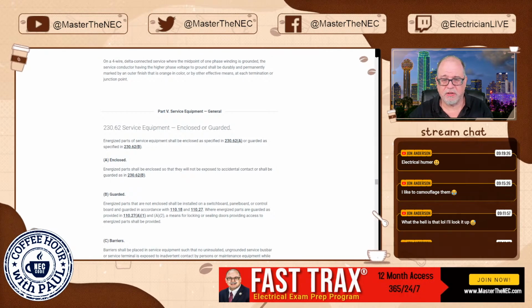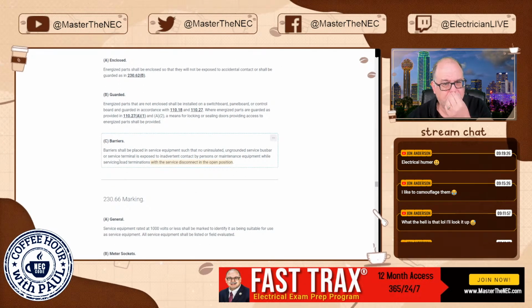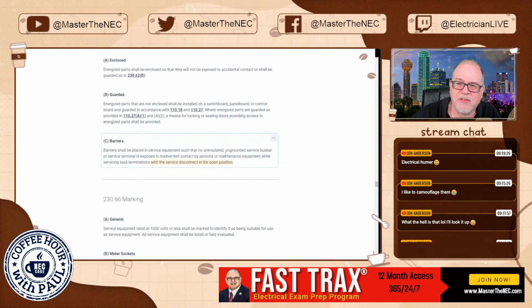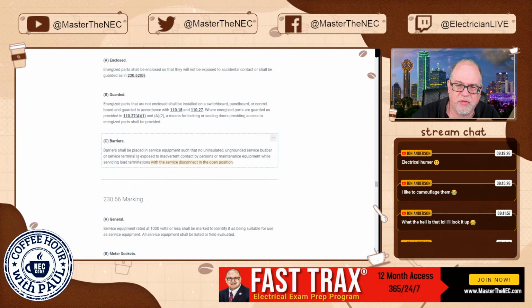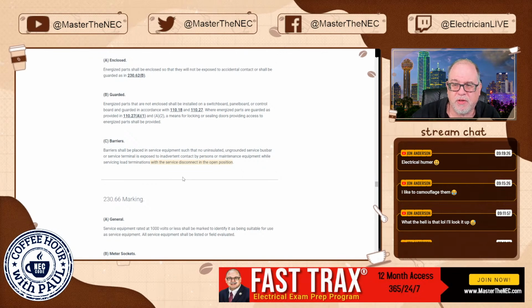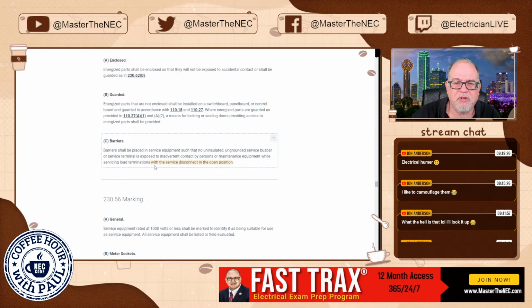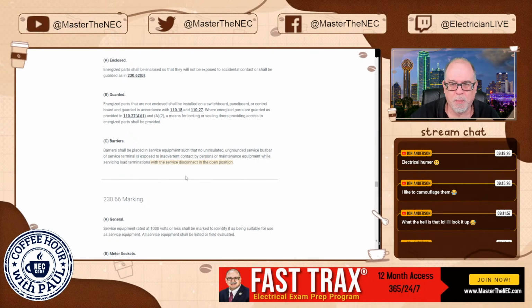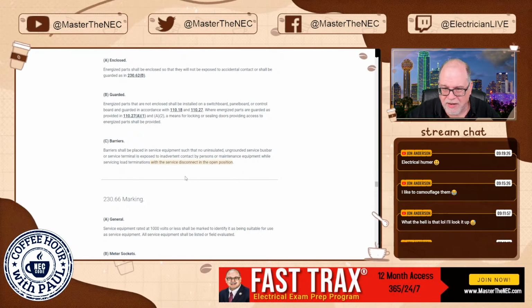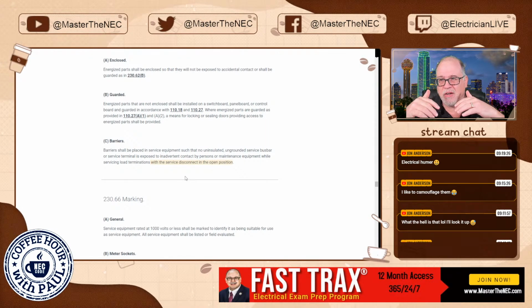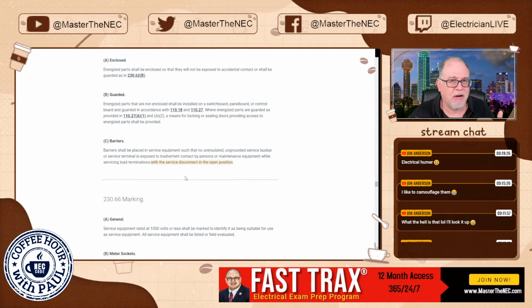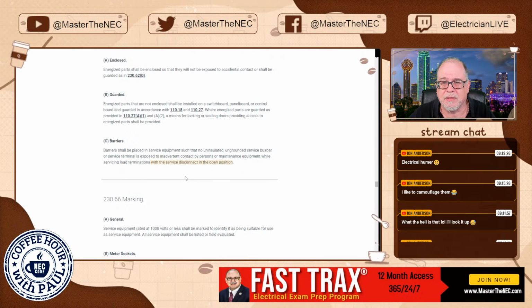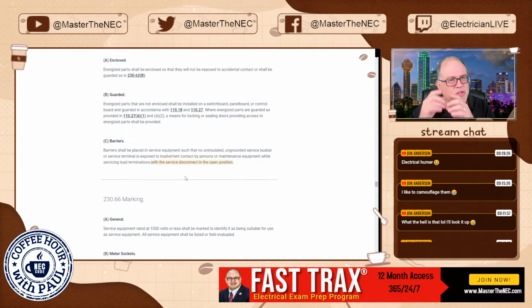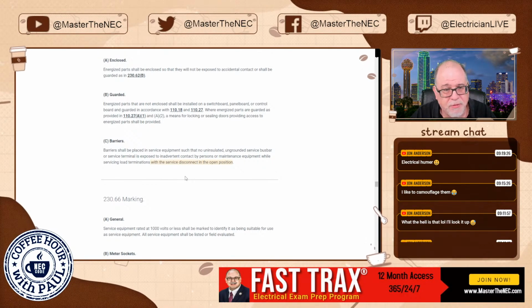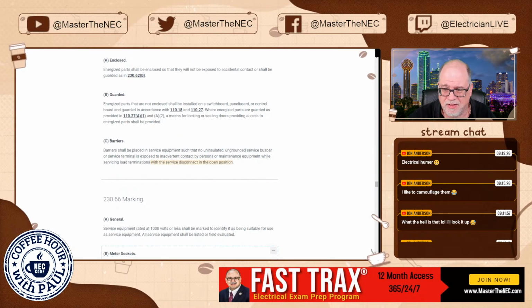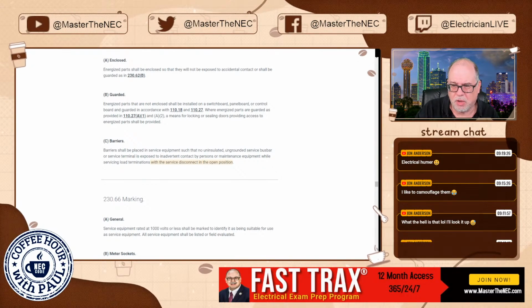Okay, so there's been a revision here in C. Let me scroll up so you can see this real quick. It says barriers shall be placed on service equipment such that no uninsulated, ungrounded service bus bars or service terminals is exposed to inadvertent contact by persons or maintenance equipment while servicing load terminations with the service disconnect in the open position. And look, y'all are already used to this. So you've got service equipment and it has the lugs. The lugs, the conductors that are supplying it, they don't have any short circuit and ground fault protection, right? They have overload protection because they're connected to an overcurrent protected device, right? You're limiting the load. But those lugs are still live. Even when it's open, those lugs are still live. Now, you're already familiar with this. This part isn't new. This last sentence is new, but y'all are already more than familiar with this, okay?